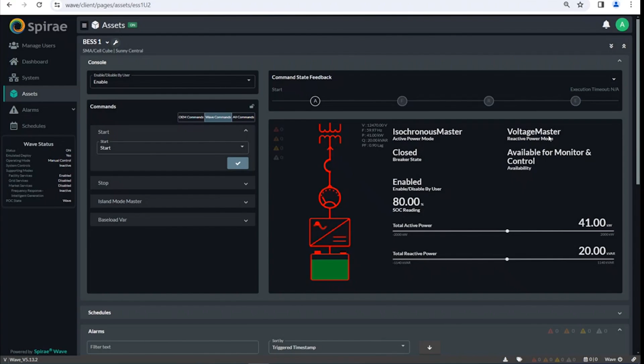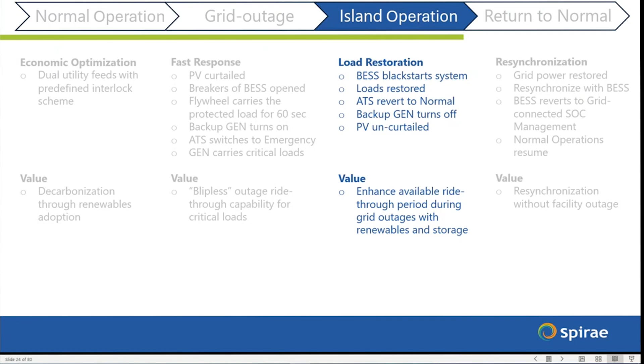And if you dive into this ATS situation, you will see it switch back to normal, and also the emergency gen is shut down. And let me change the system to auto control so the voltage and frequency of the system will be monitored by Wave. So this strategy extends the available ride-through period during grid outages by leveraging renewables and energy storage.